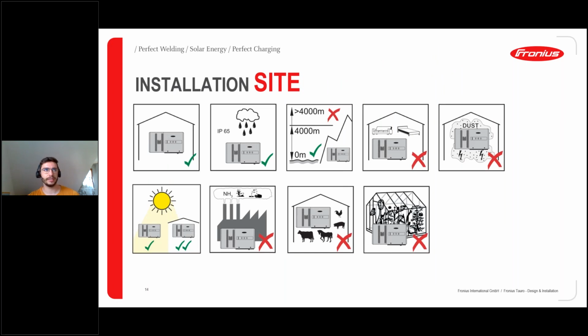Regarding installation, indoor or outdoor is no problem with the IP65 class, and also altitudes up to 4,000 meters without restrictions. We have an actively cooled system, so there is some noise, which is why we don't recommend installing it in living areas. Also, it's not good to install it in areas with high dust production, because the cooling channels might get clogged, so we need to make sure it's not too dusty there.